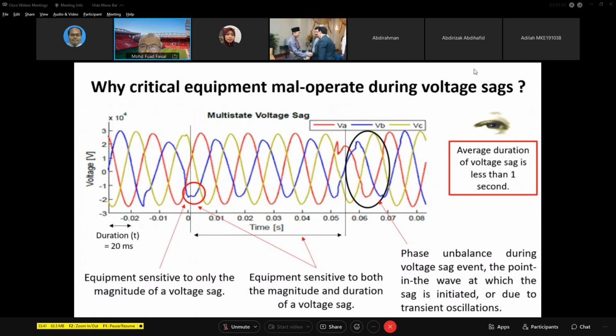Okay, this is also a very important study done by many researchers on why every time the light blinks, equipment will stop. There are basically three main causes. The first one is very dependent on voltage magnitude. If, for example, the equipment requires 11 kV, but then when the voltage slightly reduces, it will malfunction. Okay, the next one is due to both magnitude and duration. If the voltage reduces for a certain duration, equipment will be affected.